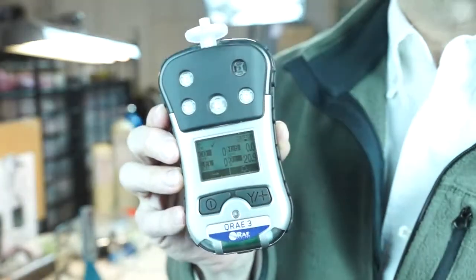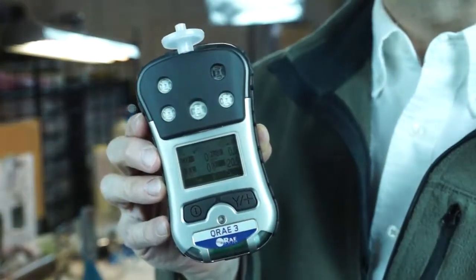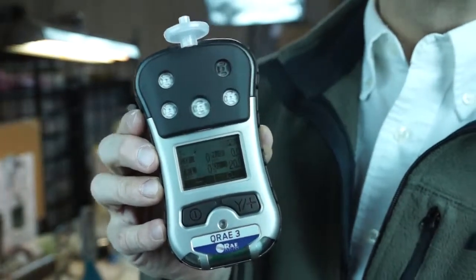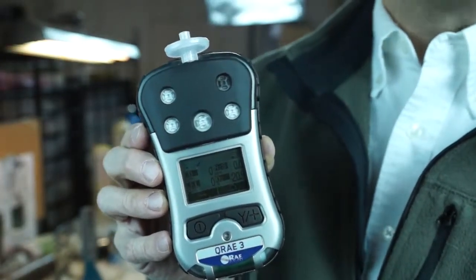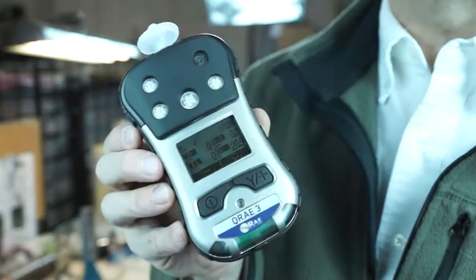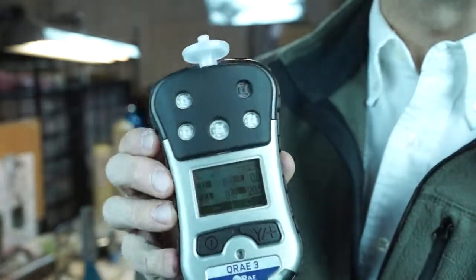The QRAE 3 is a four-gas instrument, or at least can have up to four gas sensors put in it. We can configure this down to a minimum of two, but it does have a spot for four. Traditional LEL, O2, carbon monoxide, and H2S sensors are the standard package. However, hydrogen cyanide and sulfur dioxide combinations can also be used.